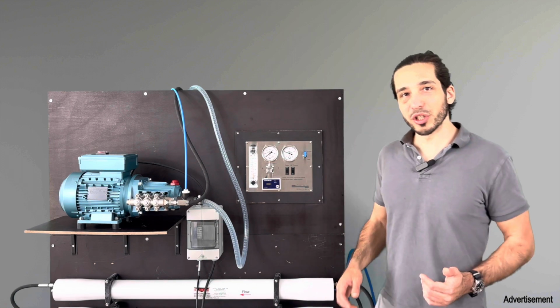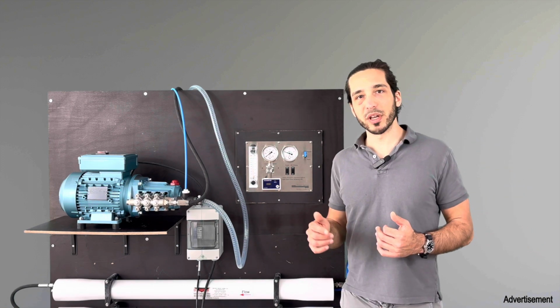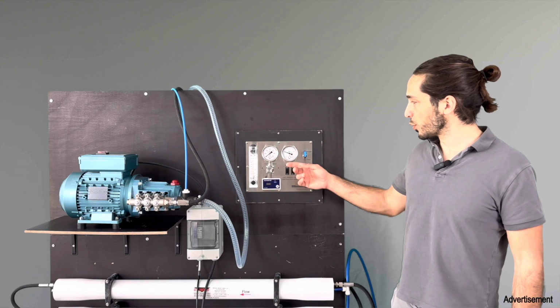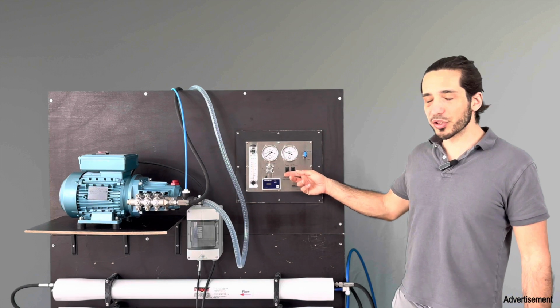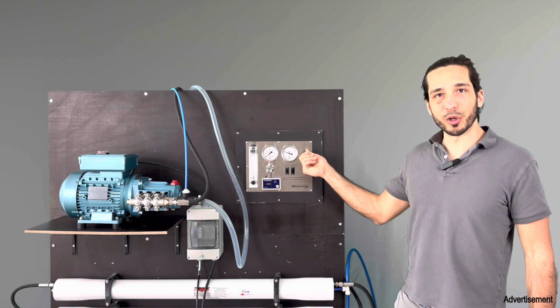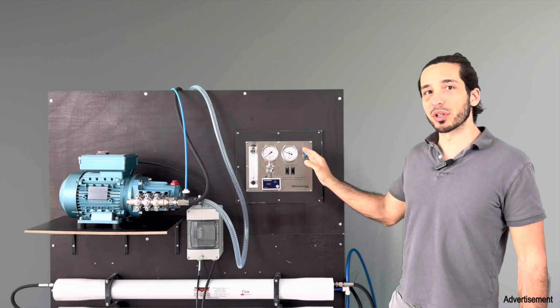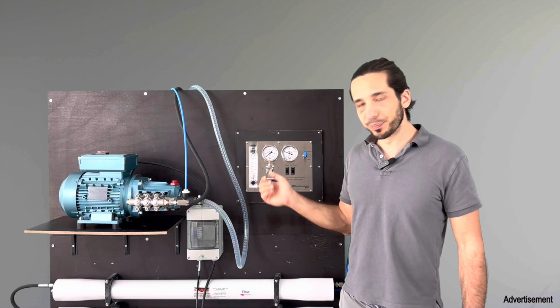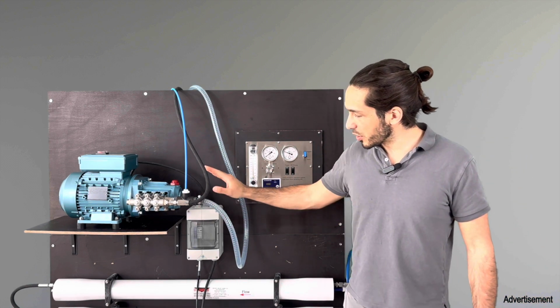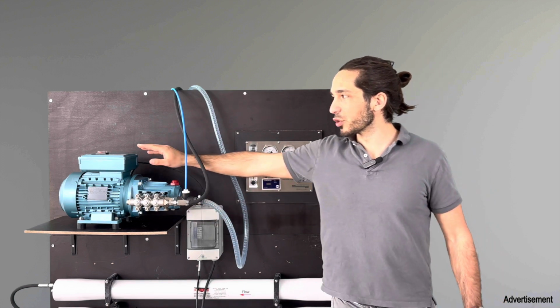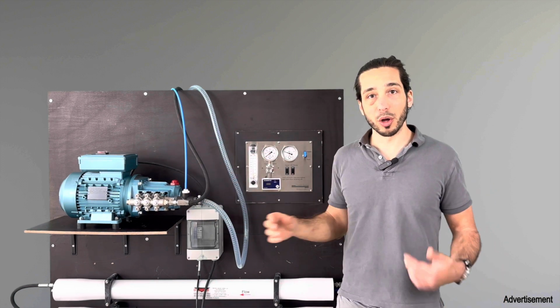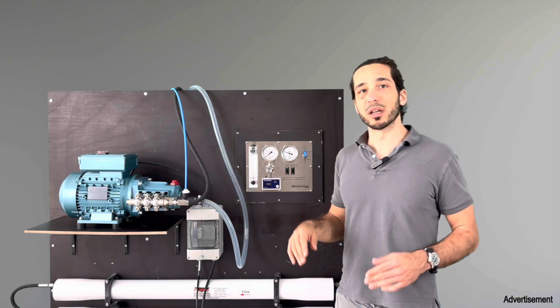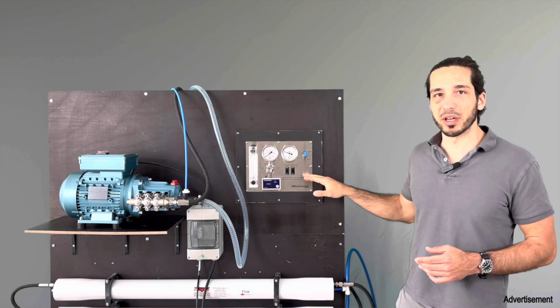So when we got a freshly installed unit, before we start we want to make sure a few things. First, make sure the switches on the control board are in their off position, the product water valve is in a raised position, and the pressure regulator is all the way open. Next, you make sure that the switch in the control box and the switch on the motor unit are both in their on position. They should remain like that, and then the control is only done via the control panel.